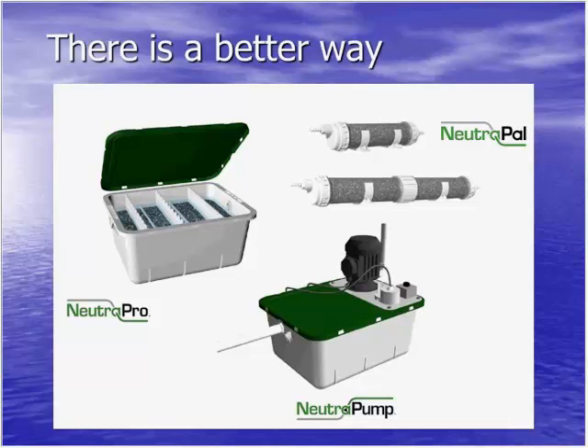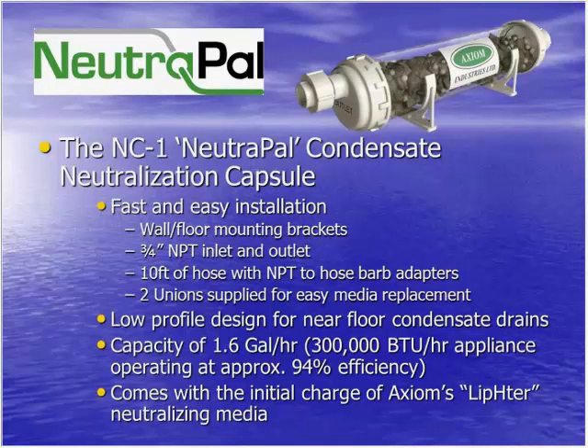It's called the NC-1 NeutraPal condensate neutralization capsule. Comes with everything you need to install. Floor and wall mounting clamps, 3/4 inch NPT inlet and outlet connections. We also provide it as a kit with 10 feet of hose that comes with NPT hose barb adapters. And two unions are supplied with every unit as well for easy media replacement. In each of our capsules, we actually have a screen that holds the media within the capsule to prevent that media from clogging the inlet and outlet of the capsule.